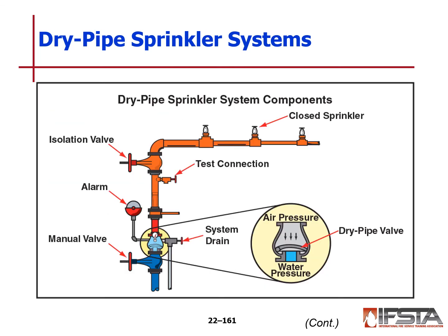In a dry pipe system, the system is not charged with water at all times. In these systems, there will be pressurized air in the system. The dry pipe valve is designed so that if a head opens and the air pressure drops, the water pressure will then overcome the valve and open it up.